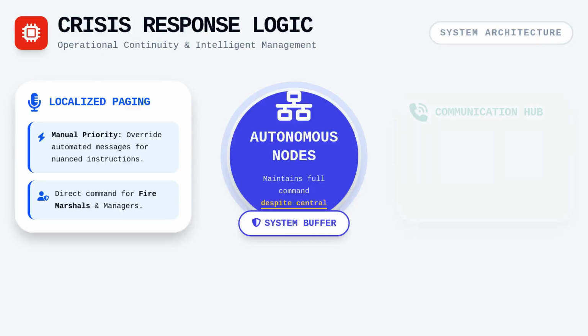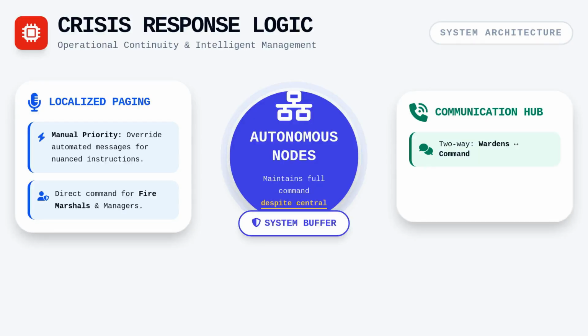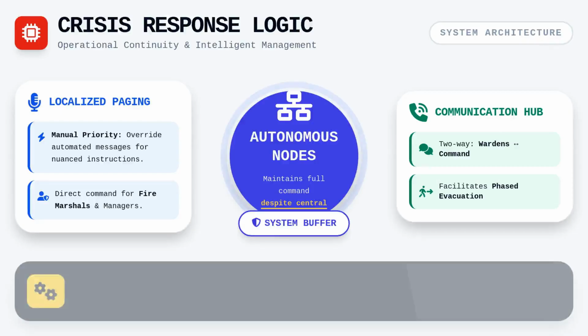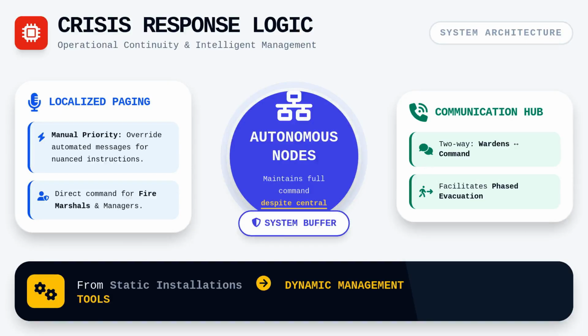Firefighter telephone systems extend this capability by allowing two-way communication between floor wardens and the primary command center. Properly integrated, these systems transform a static fire alarm installation into a dynamic management tool that can steer populations away from danger and facilitate a controlled, phased evacuation.